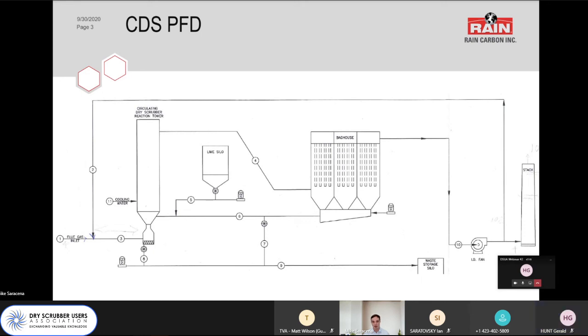Yeah, the way we approached that was we modeled our emissions, and that's the way it's recommended to handle it. You effectively model your emissions and make sure that whatever parish or county you're in is in attainment for the majority of the year, up to whatever the government says. The issue operationally is that we have internally found that concentration really seems to drive the dispersion of the SO2 itself. Temperature has a high impact, flow has a high impact, but what we actually control our stacks to is concentration. And that's an inherent problem because concentration is a function of both flue gas flow and mass flow of SO2.